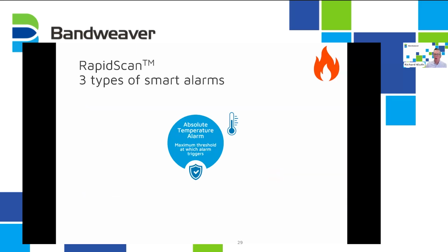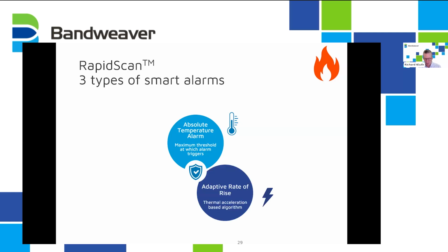So the three types of smart alarms: we have the absolute temperature alarm. This is probably the most similar to conventional heat detection, where you have a temperature, and if it goes over that temperature, the alarm sounds. With ours, it's fully programmable for each zone, whereas often with conventional heat detectors, it's not programmable. So we have an advantage there, but it's similar to that.